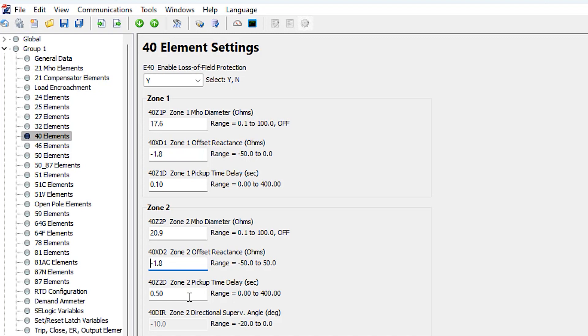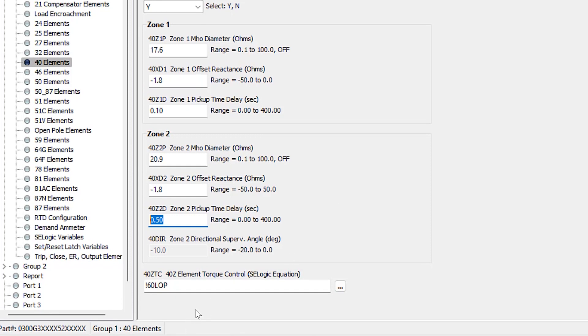The delay for zone one is 0.1 seconds to ride through switching transients. The zone two element is set to 20.88 Ω, equal to the synchronous reactance of the generator, with the same offset of −1.81 Ω. We hit Enter and the relay rounds to one decimal place — the error from before goes away. The delay for zone two is 0.5 seconds to prevent tripping during power swings. To summarize: offset for both zones is −½ X'D, zone one = 1 pu on machine base, zone two = XD, all converted to secondary ohms.